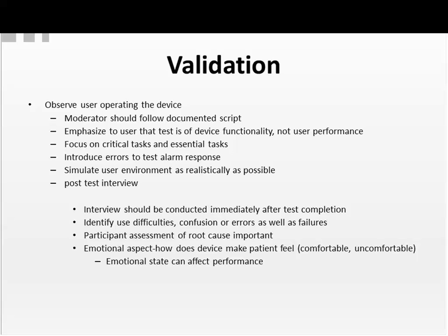In the validation, you focus on critical tasks, essential tasks. You will introduce errors to test alarm response. How does the user respond to an alarm? What does he do? You simulate the use environment as realistically as possible, and you have a post-test interview.